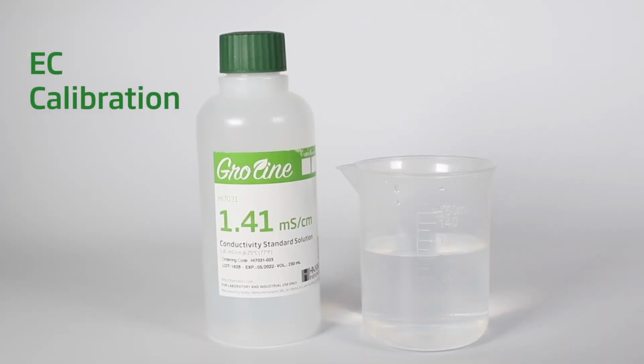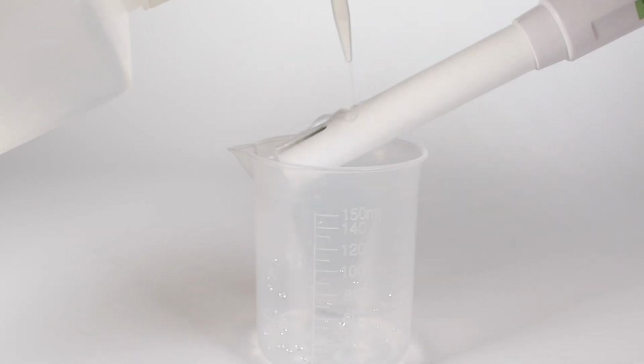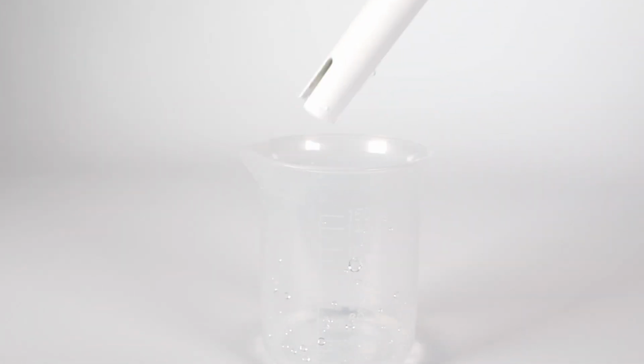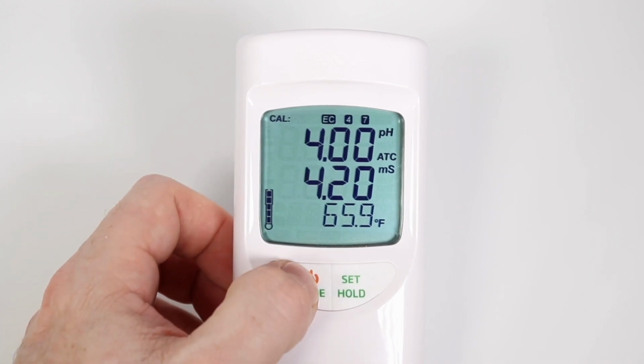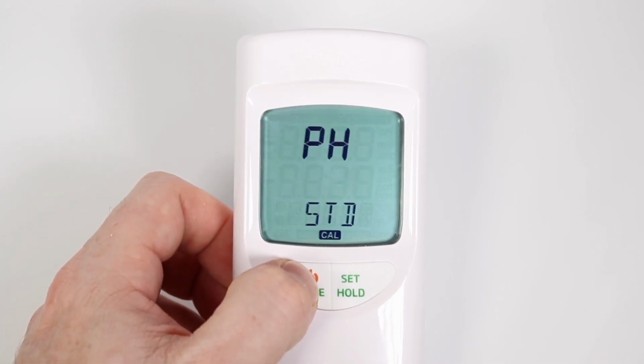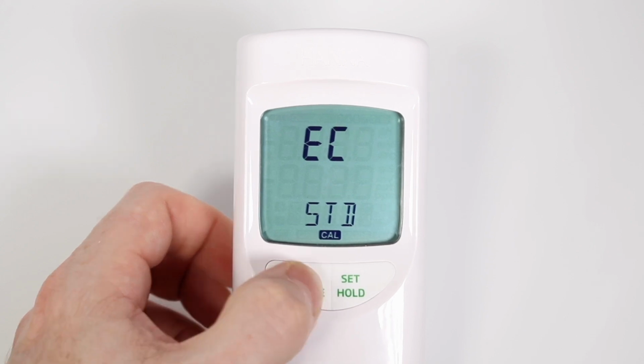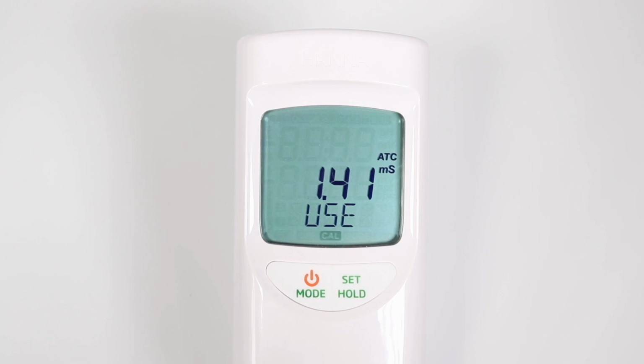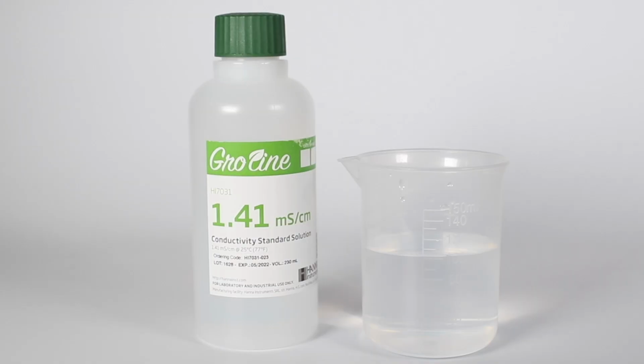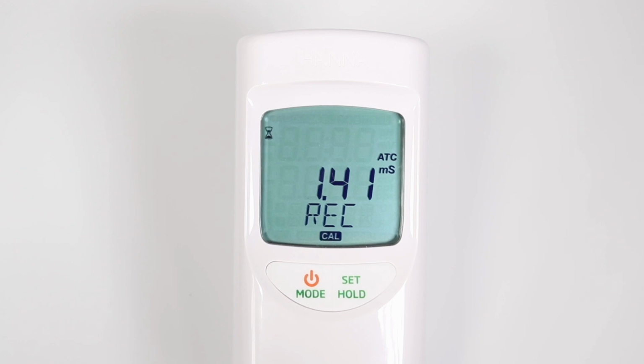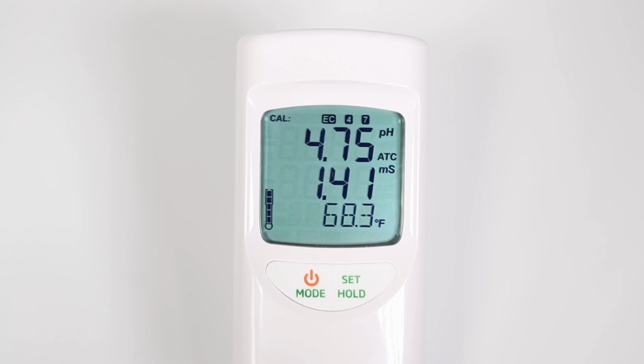Now let's calibrate for EC. Rinse your probe for 10 seconds with distilled water to dissolve any KCl, potassium chloride, crystals left from the storage solution. Tap water is okay if distilled is not available to you. Hold mode until EC standard appears. Release the button. Immerse the probe in the 1.41 millisiemens or 5.0 millisiemens calibration solution. If the standard value is recognized, REC is displayed. Then wait blinks until the calibration is accepted. The LCD will display Save for 1 second and return to normal measurement mode.